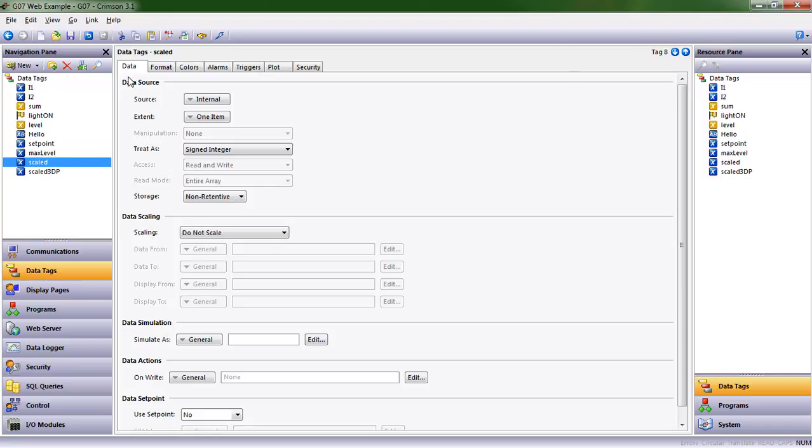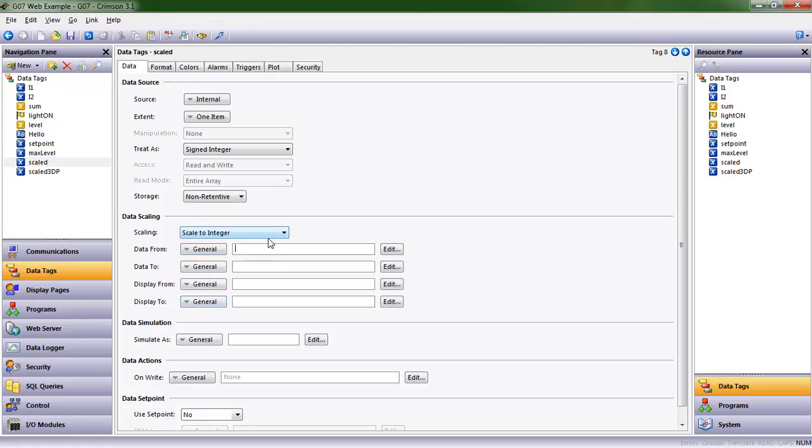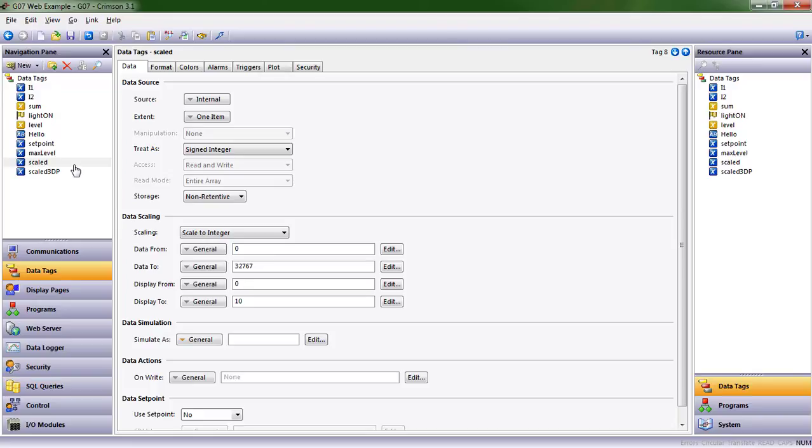My analog value is going between 0 and 32,767, but we want to see that as a scaled value between 0 and 10. Let's look at our scaled value. On the data tab, there's a data scaling area. We have Do Not Scale. Let's scale it to an integer, and the input can be between 0 and 32,767. To us, that means 0 to 10.